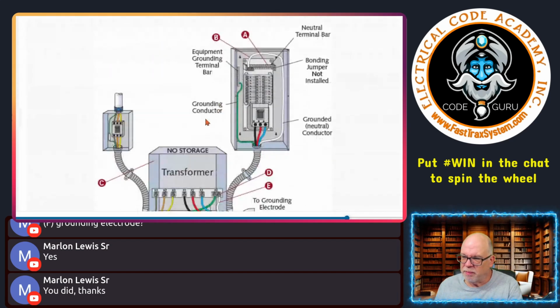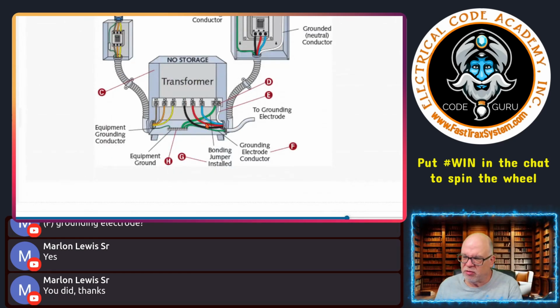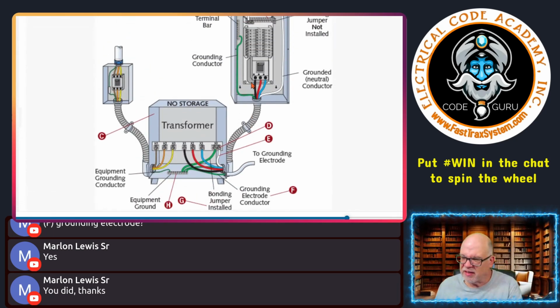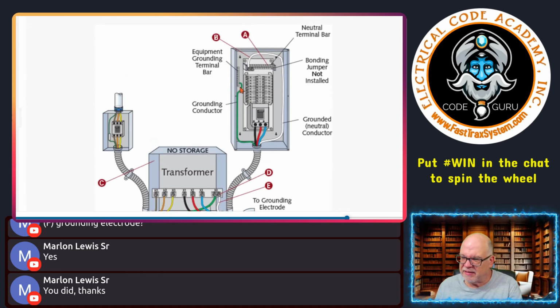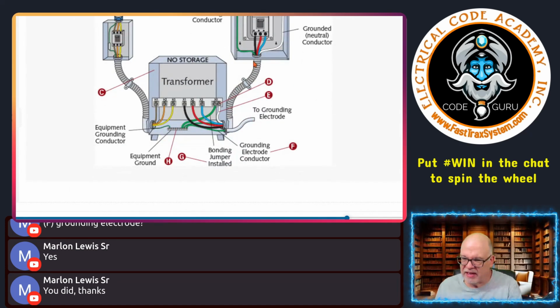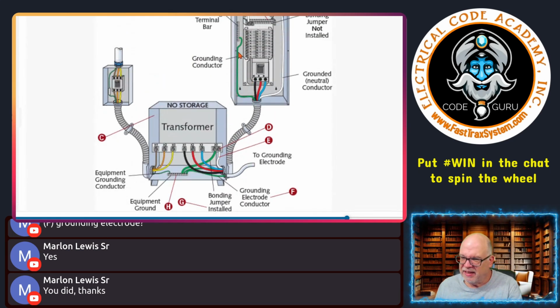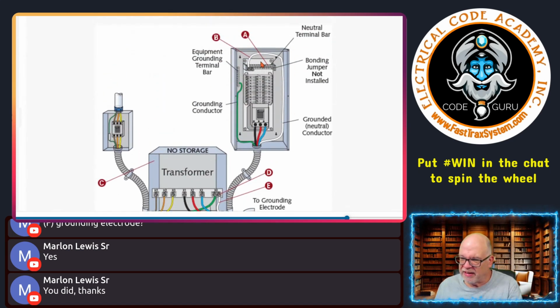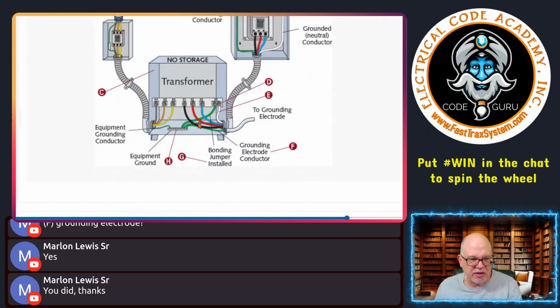In this case, it would be required. This one right here, you'll notice we got all this running up. Supply side, because of this flexible FMC, we have a supply side bonding jumper, so that's required. Up here, the neutral bar is isolated. This one is connected to the enclosure. Why? Because the system bonding jumper is down here. Got it. So we got all that.